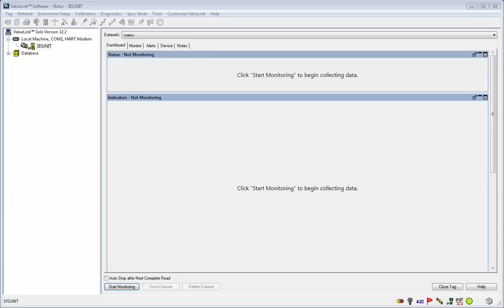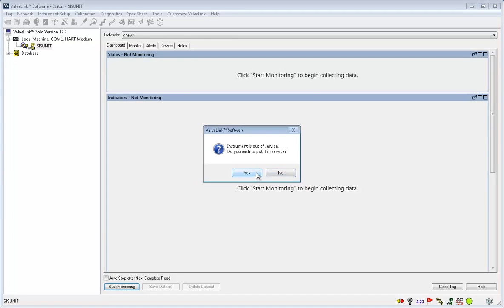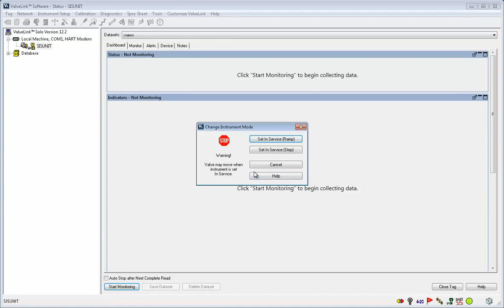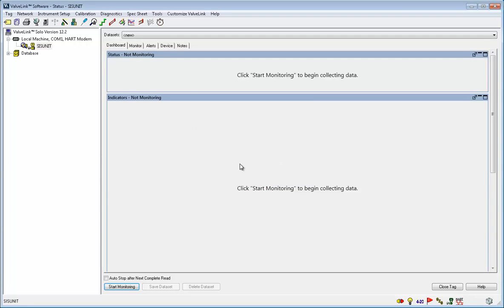Once the calibration process is complete, you can put the instrument back in service. Click OK, and then click Yes, and click Set in Service Step to put it back in service. Now we are done. We have successfully set up and calibrated the DVC6200SIS using the Setup Wizard.